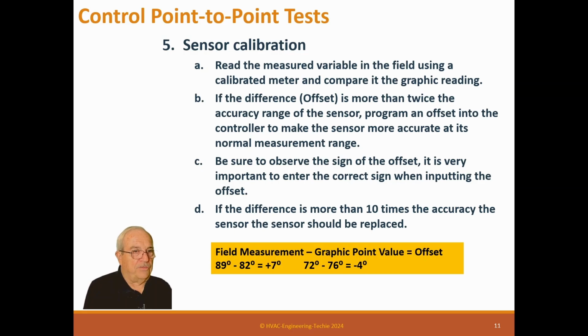The formula is the field measurement minus the graphic point, and that's how you get the sign. So if you read it in the field, it's 88 degrees, 89 degrees, and in the screen it's 82 degrees, then it has an offset of +7, okay? If you read 72 in the field and a 76 in the office, it's a -4 degrees. So the sign's really important.